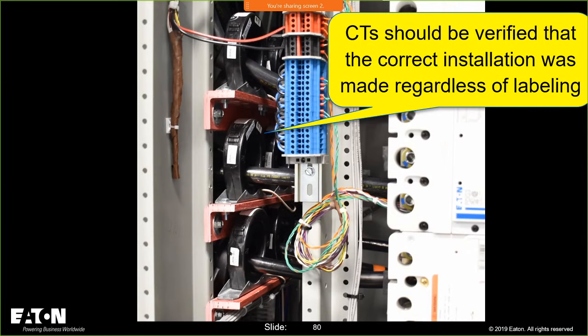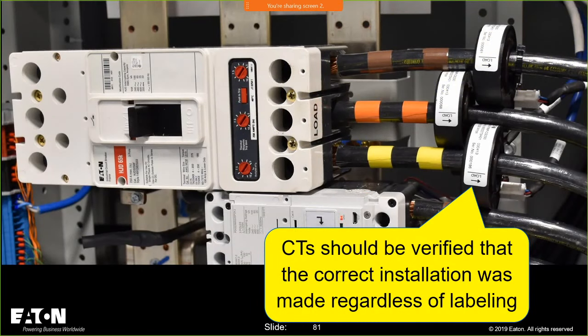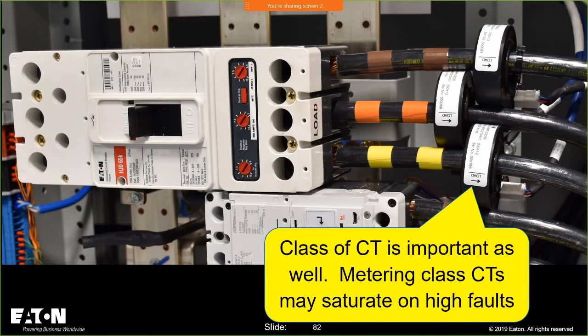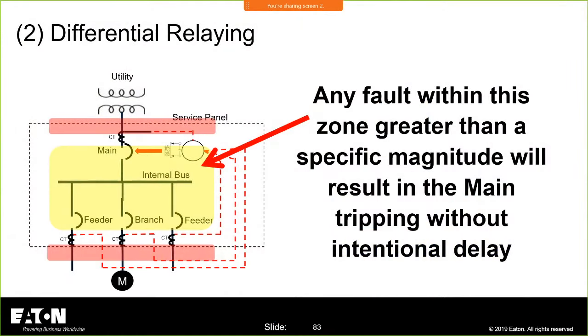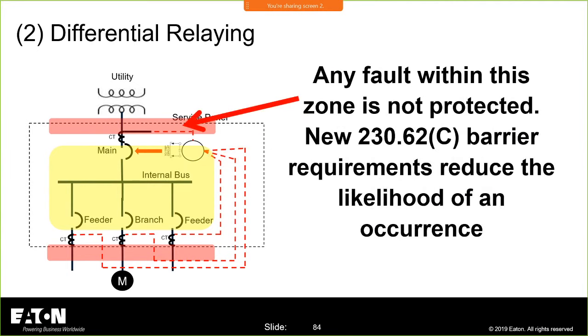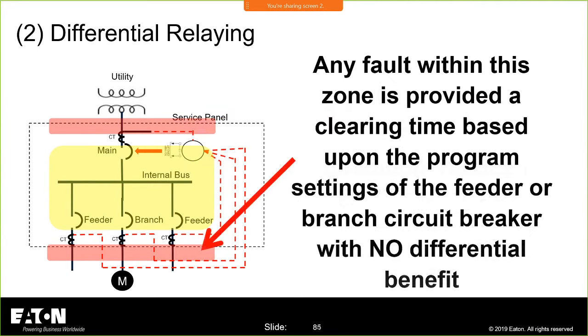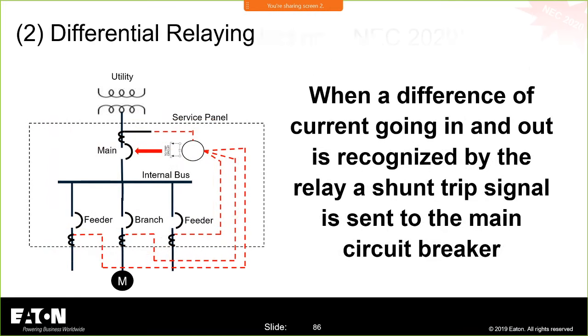You have to verify the CTs. You've got to verify those labels. They may not be right. Make sure you have a metering class CT or a relaying class CT. Metering class CTs will perform a little differently. They'll saturate at your higher fault currents. You're going to need a relaying class CT for these things. Don't mess that up either. Right? And then you have zones of protection. It's important to understand the zones of protection and what you're getting.